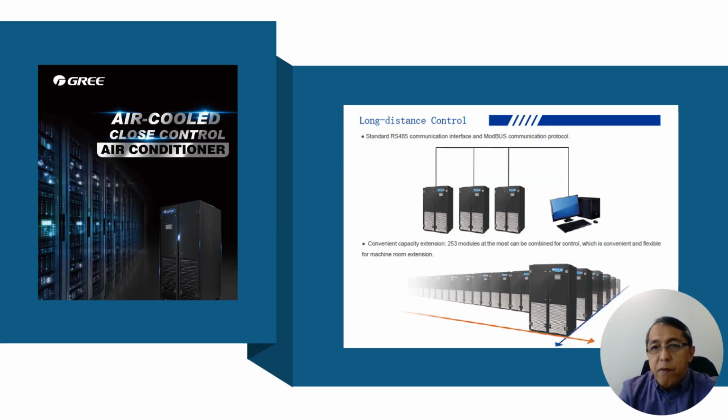It is also capable of long distance control, such as the utilization of standard RS485 communication interface and Modbus communication protocol. It also has a convenient capacity extension, up to 253 modules at the most can be combined for a single control, which is convenient and flexible for machine room extension. So if you want to do a remote monitoring, it's possible.